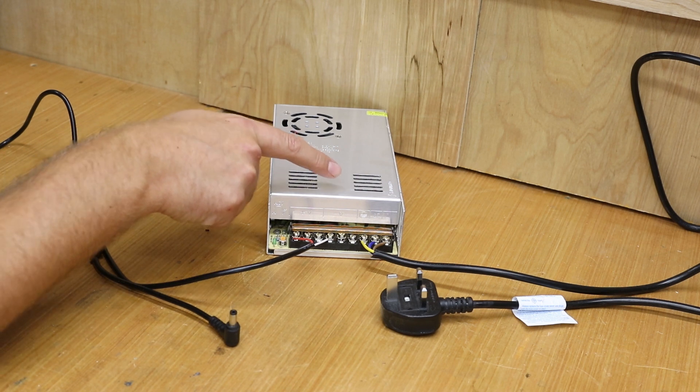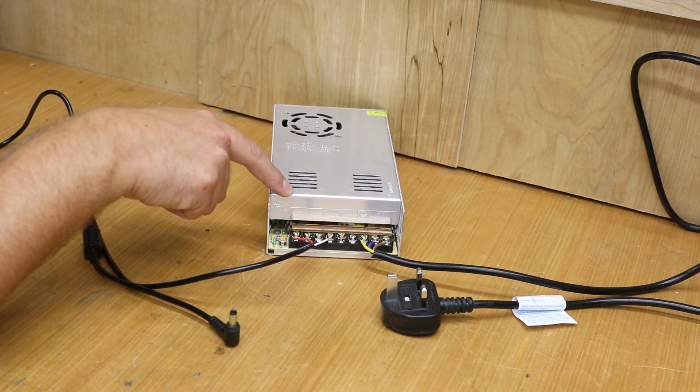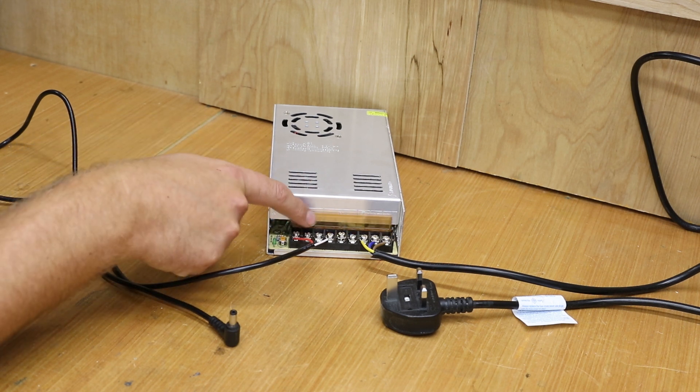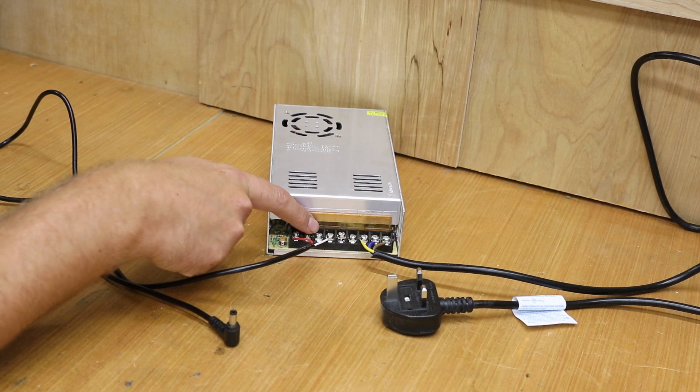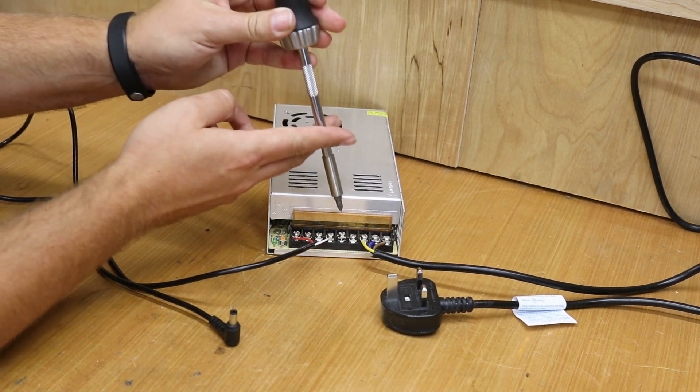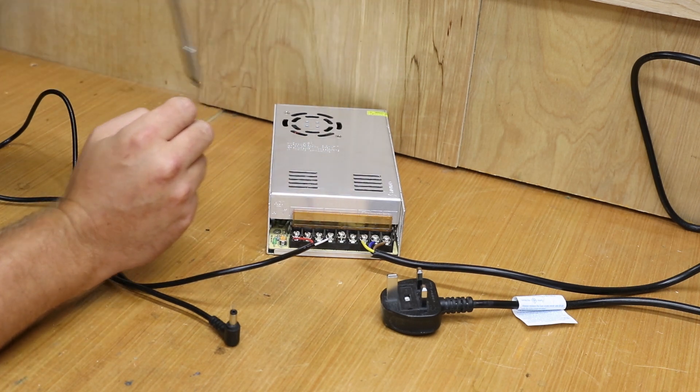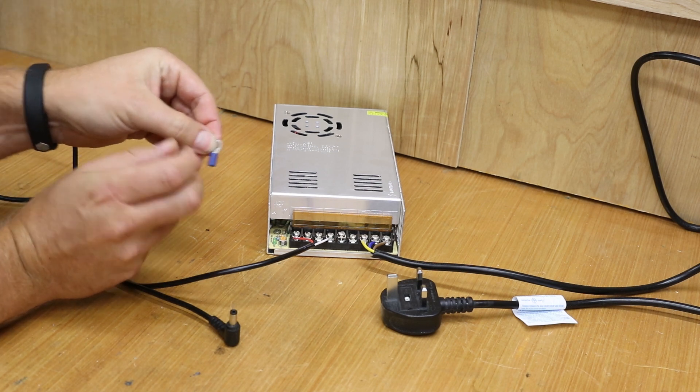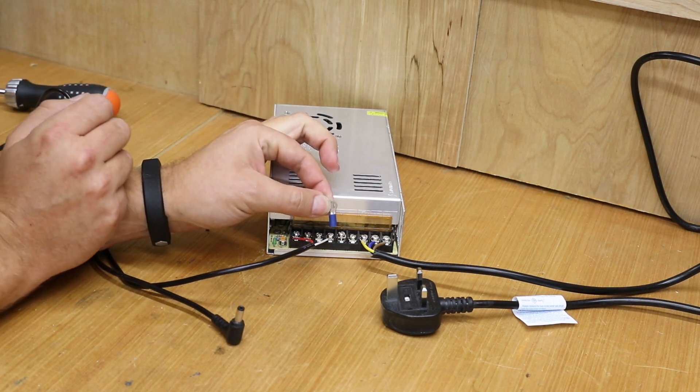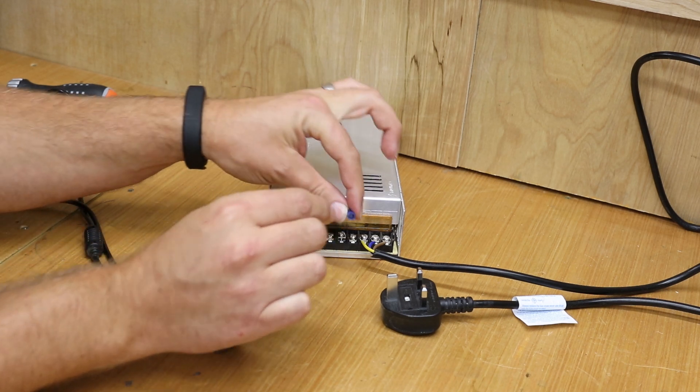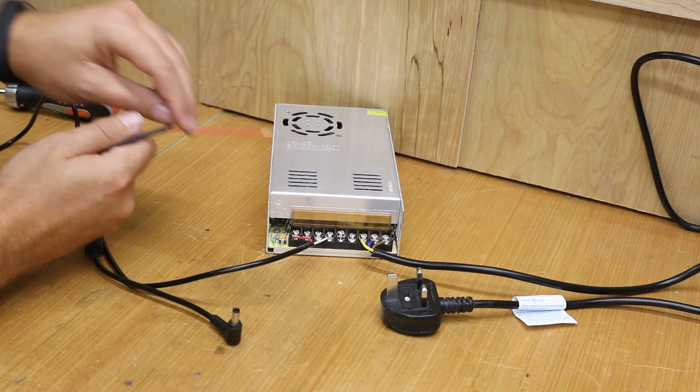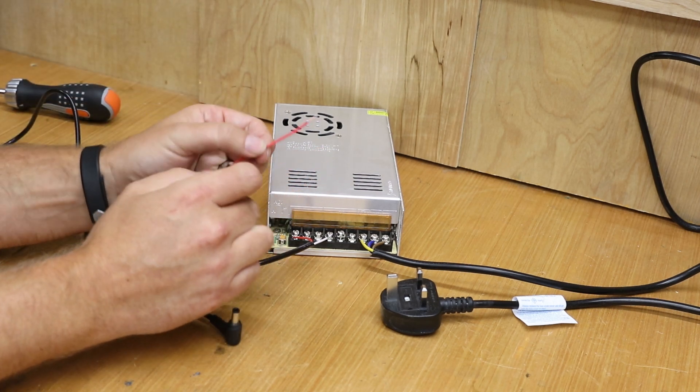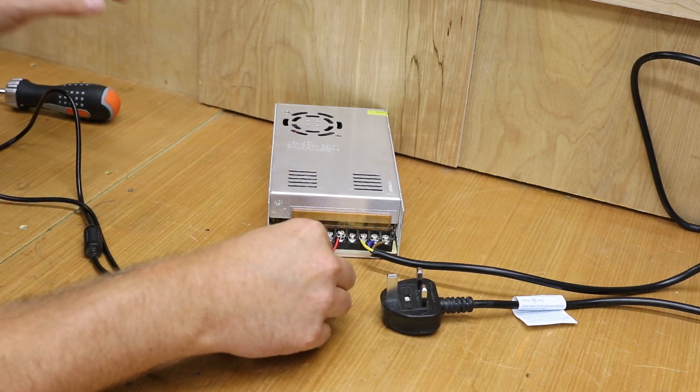Now the first 3 are the negative or neutral, and then the next 3 are the positive or live. To actually connect to them themselves you simply lift the plate up and you can release the screw and clamp plate just by undoing them. Now to connect the wires themselves you've got two choices. You can use terminal connectors like these, either the little circle ones or the U shaped ones, and they will simply go straight into the port like that. Or you can strip back the wire so you've got the exposed copper wire, and then you put that in between the clamp plate and simply tighten the clamp plate back up.